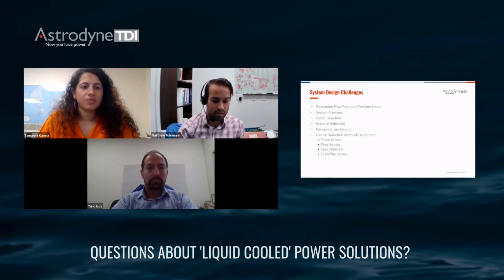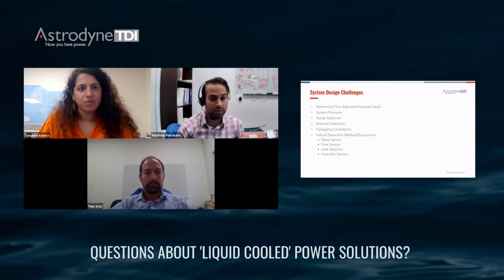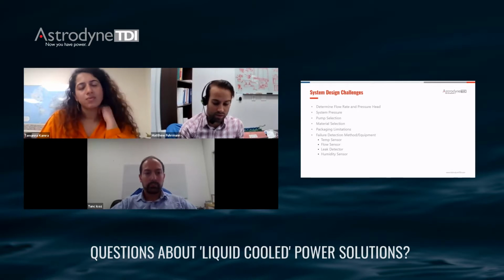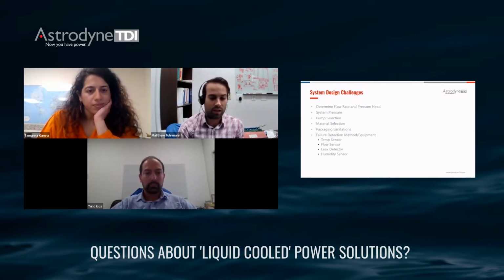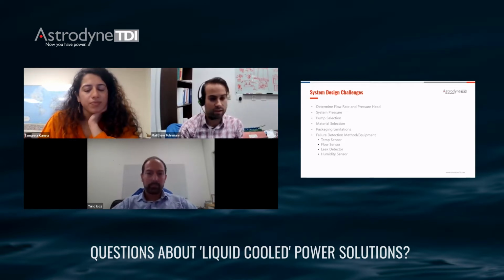So if you're concerned that you have a blockage somewhere, you can place thermocouples along your manifold or along some of your fittings, and monitor the temperature coming in or going out of your heat load. You can also include a flow sensor to make sure that you're getting the right distribution to your power supply.